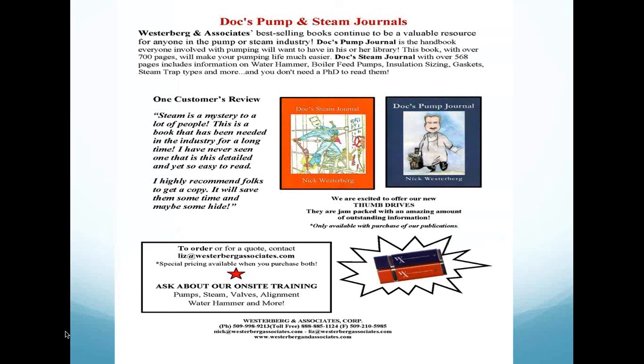If you're here today and you picked up anything, even one nugget, when I start a class, I usually try to tell the good folks that come, if you can just take one nugget away, whether it's you can lift condensate 2 feet for every pound, or whether it's you've got to be careful and make sure that you use vacuum breakers and air vents to stay away from condensation-induced water hammer, then hopefully you will feel that this time was worthwhile.